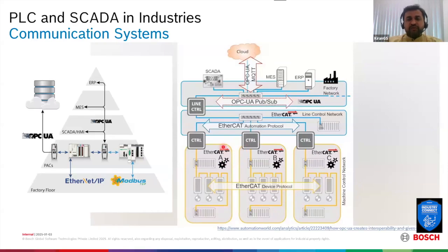So likewise, if you see, these are connected to the controller and then going to the line level controller. Typically, you will have either the EtherCAT or OPC UA communication protocol. Of course, there are trends going on from OPC UA even to MQTT for higher level communication. So from a communication angle, when you deal with PLC and SCADA systems, you should also be aware that your program is compatible with these kinds of communication protocols. And it should also have the flexibility to connect to other systems in multiple ways.